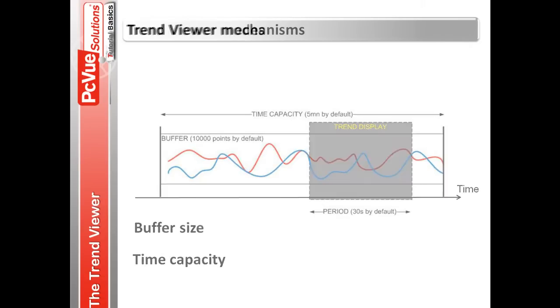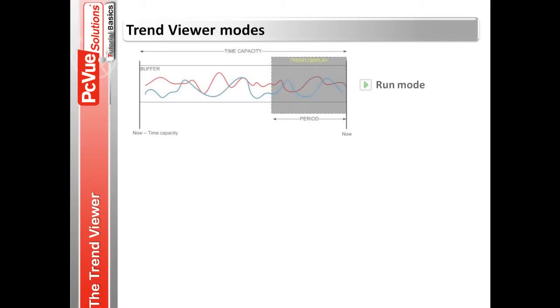The trend viewer operates in three distinct modes. The run mode displays the trend in real-time. And the trend viewer focuses on the right-hand position and displays the points that are coming in. The display buffer temporarily records values for the traces, giving the user a limited ability to scroll back in time.